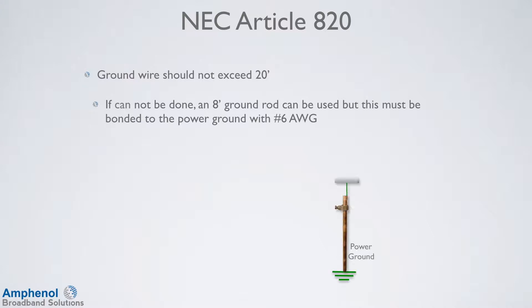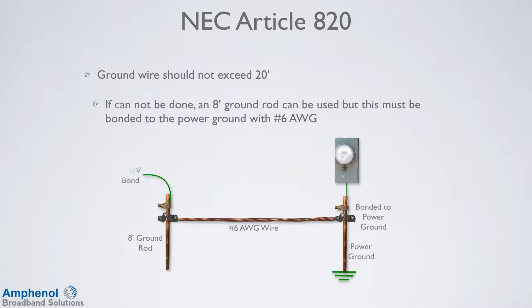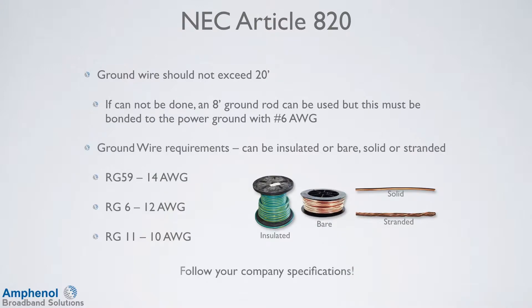Ground wires should not exceed 20 feet. If that can't be done, an 8-foot ground rod can be used, but this must be bonded to the power ground with a number 6 gauge wire. This is when a cable TV company would drive a ground rod on a residential or mobile home, but only on rare occasions. We'll show seven different bonding options later, and one of them should enable a ground wire of less than 20 feet. Ground wire can be insulated or bare, solid or stranded. For RG59 use 14 gauge wire, for RG6 use 12 gauge wire, and for RG11 use 10 gauge wire. Check with your company's installation standards for any more stringent requirements.